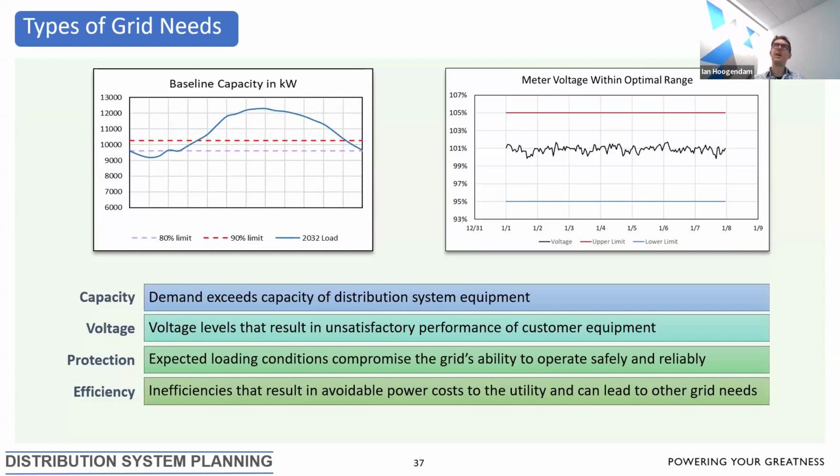So the area above the red line, that load profile, is the persistence of the grid need over a course of a forecasted peak loading day. So when we're looking at solutions for this, a traditional solution might be to increase the wire size, which would add more capacity, effectively raising that red line. Where if we were looking at a non-traditional solution, we would be focusing on lowering the blue line by encouraging customers served from that line to participate in various energy programs.